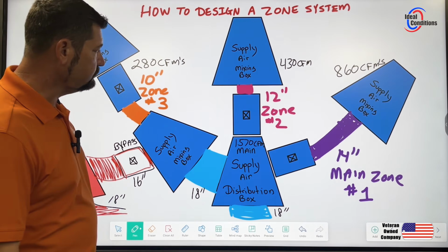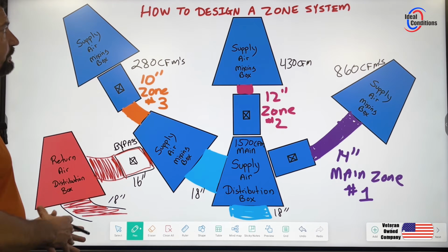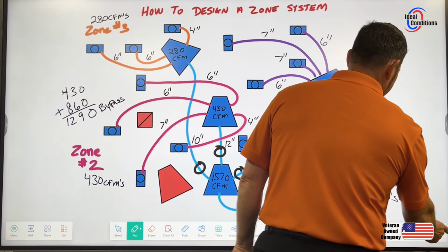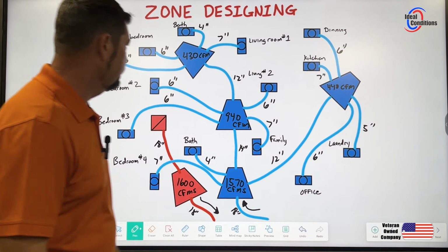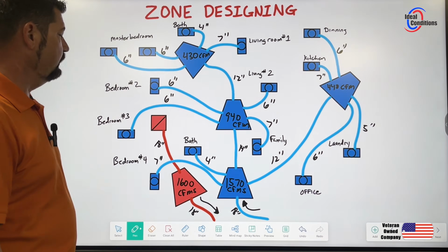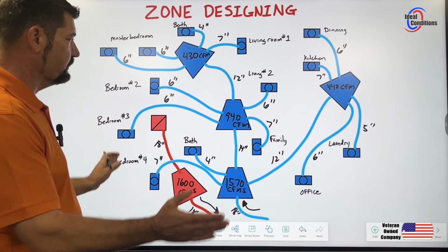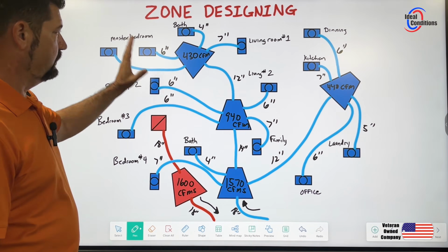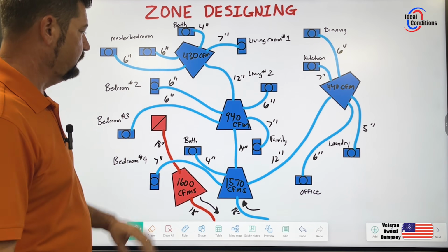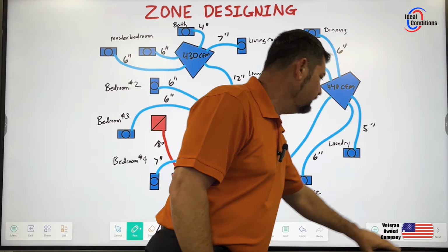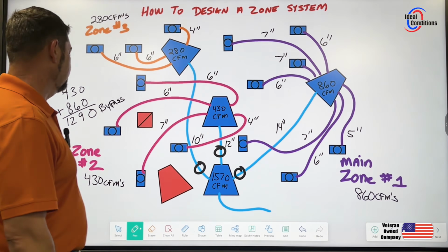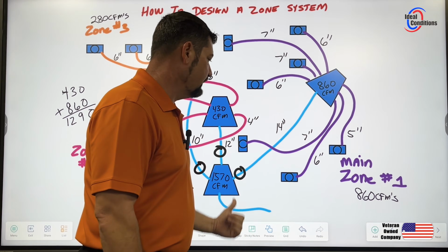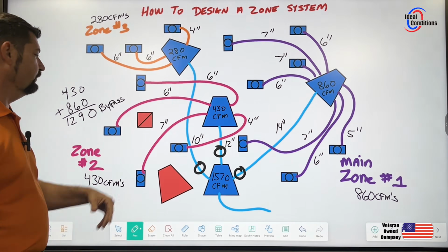See it a lot. This is just a very simple way to take something that looks very complicated. We'll come back over here and say, hey, it's already working the way it is. Everything's great. It's got a 4-ton. Everything's already balanced. Maybe need to hang it a little bit better, make it look prettier. But at the end of the day, everything mathematically is working fine. How do I take this, give the customer what they want, and allow the system to bypass the remaining trunk lines when they're in the closed position?